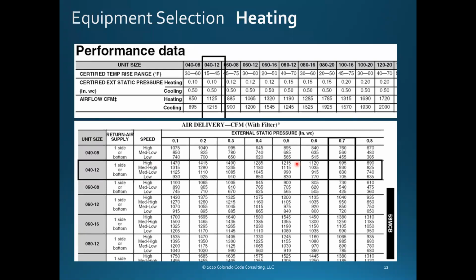The reason that this is important now, all of this stuff that we're looking at here, all of the manufacturer's performance data is all done at sea level. All done at sea level. Okay. We're going to talk about how air moves too. So we keep in mind that these are all sea level numbers, not 5,000 feet, 10,000 feet, down elevation numbers.